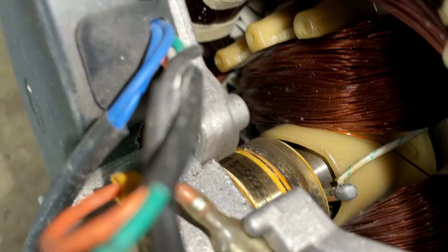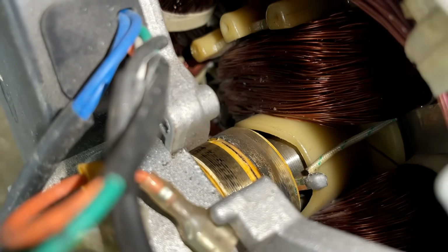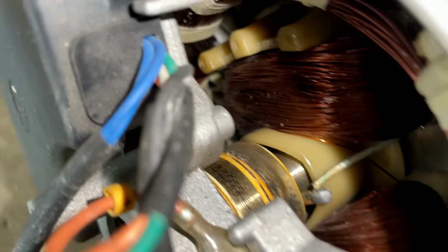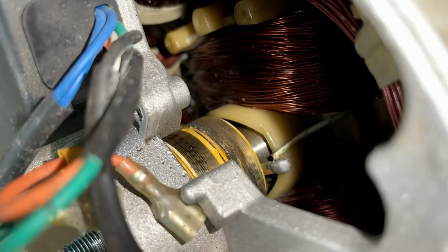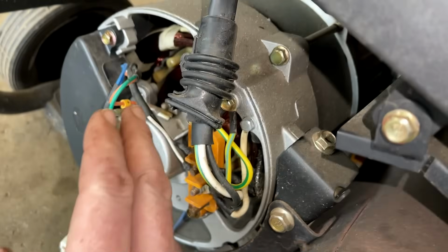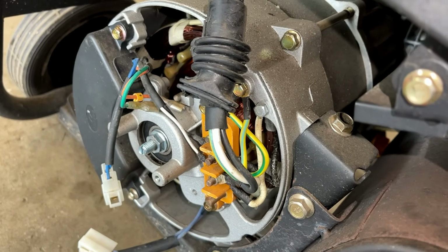It's difficult to show you the slip rings, but if you look at the slip ring on your right, that one is dirty, but it also feels quite rough, and I'm sure that was causing the arcing. So cleaning it, hopefully, will get rid of some of that roughness. Otherwise, it could be a chronic problem.